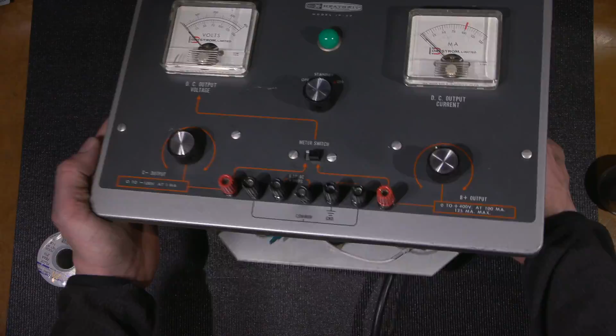The safety ground is tied to the neutral in the breaker panel. So that means this line in the breaker panel makes a connection to this line right here, and this line is directly connected to the pole. So it's not really isolating the chassis.